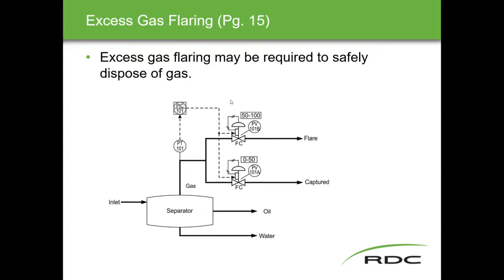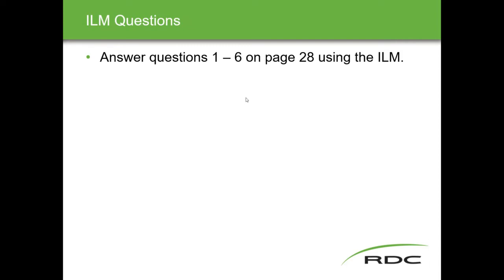The excess gas flaring example is designed to handle gas we can't collect and must send to flare. In a separator with liquid and gas products, if vessel pressure increases beyond what we can capture, the captured gas valve operates from 0 to 50% and the flare valve operates from 50 to 100%. Once pressure hits a certain level, the capture valve is fully open; if gas exceeds that, the signal keeps rising and the flare valve starts to open, so we're still capturing everything we can while also flaring any excess.